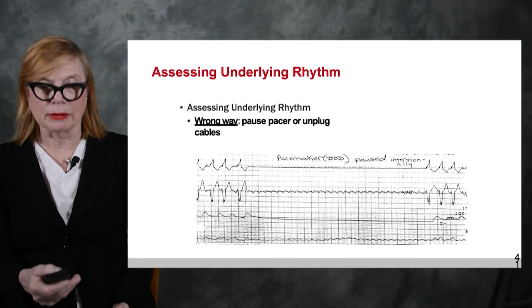So just like having an apnea setting on the ventilator, where you will not allow a patient to breathe less than 8 times a minute, turn your pacemaker rate down to around 30 or 40 so that there is always a paced rhythm if the patient has no rhythm at all. And you can see here that they pause the pacemaker or unplug the cables intentionally and the patient had no rhythm. So just turn the rate down and then turn it back up again.